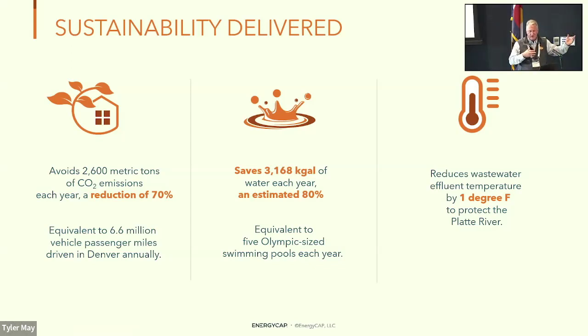When we went to Metro Wastewater and said, hey, we want to bury your sewer lines, they said, you can't do that, we're bleeding waste heat out of those lines. And as Tim said, yes, there's waste in there, but most of what's in there is hot water from showers, washers, dishwashers and clothes washers. So they spent a lot of money not just cleaning it before they can put it back in the river, but cooling it down so it doesn't harm the ecology.